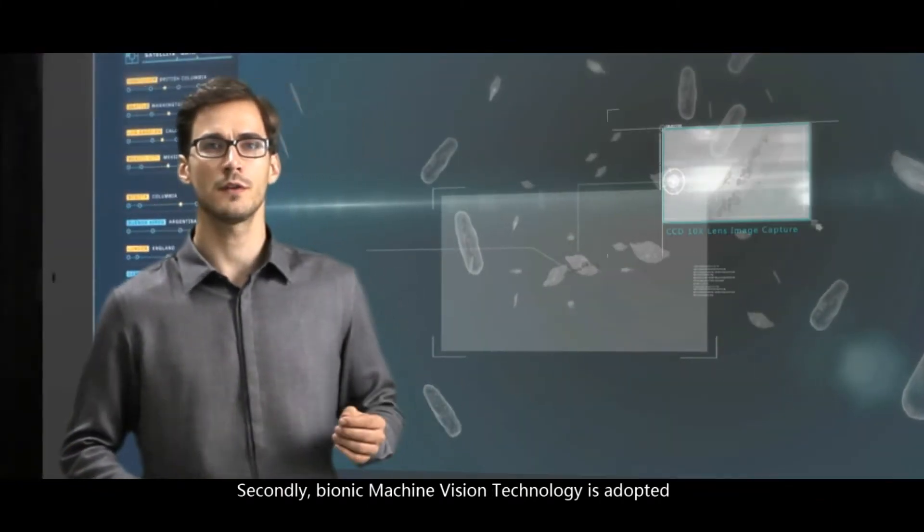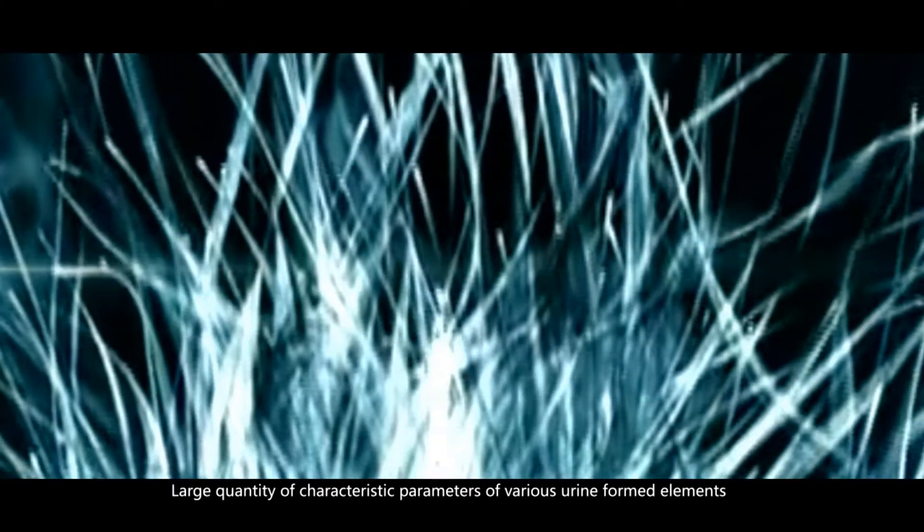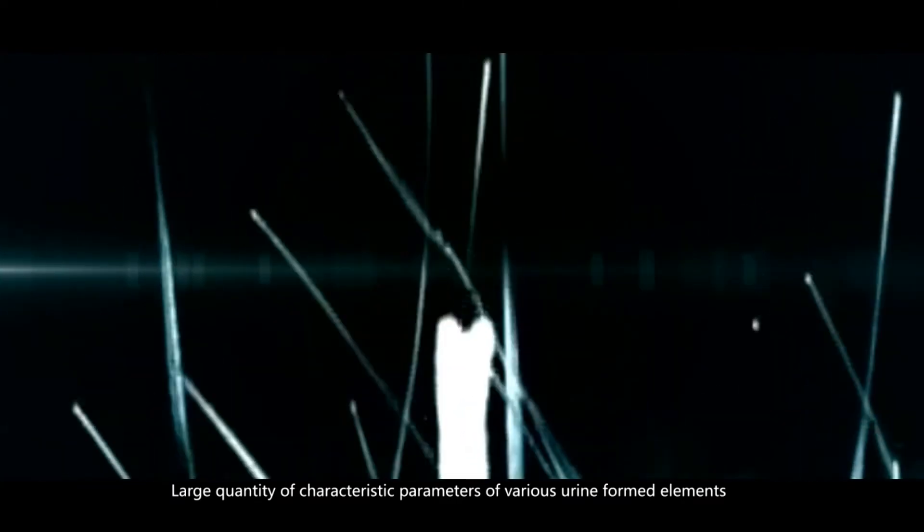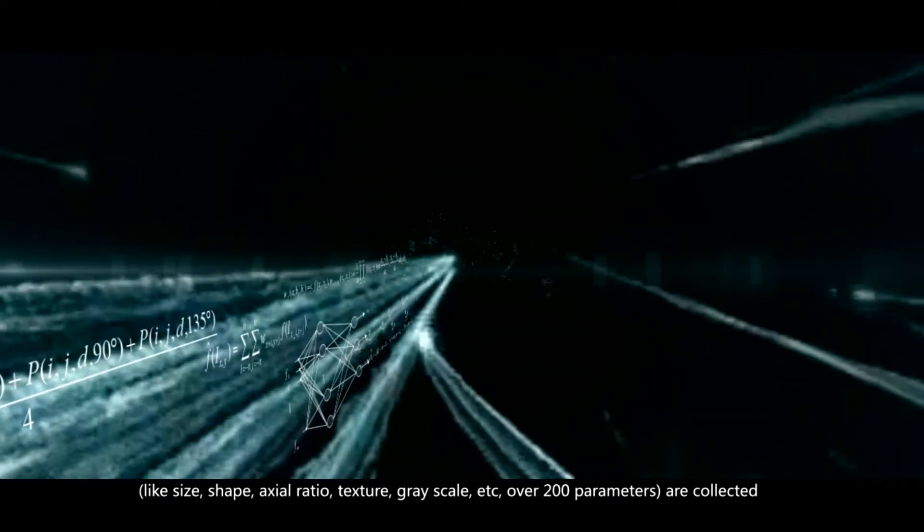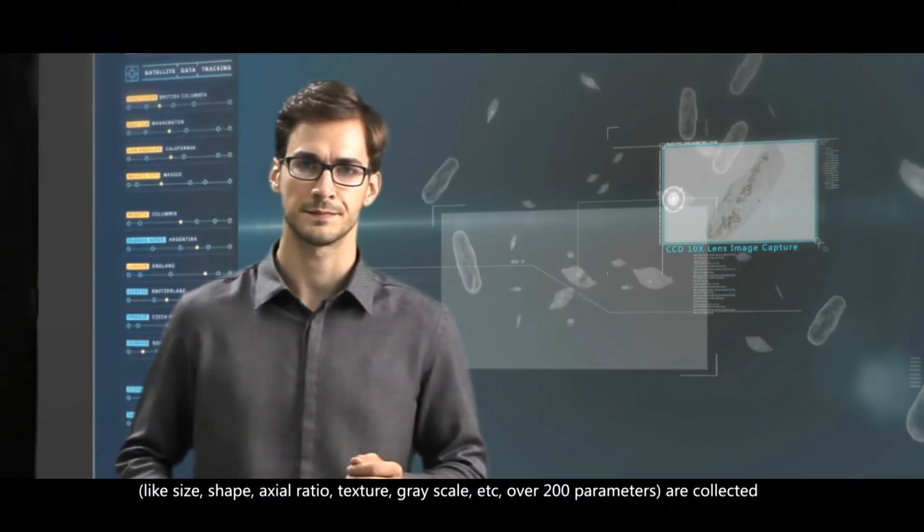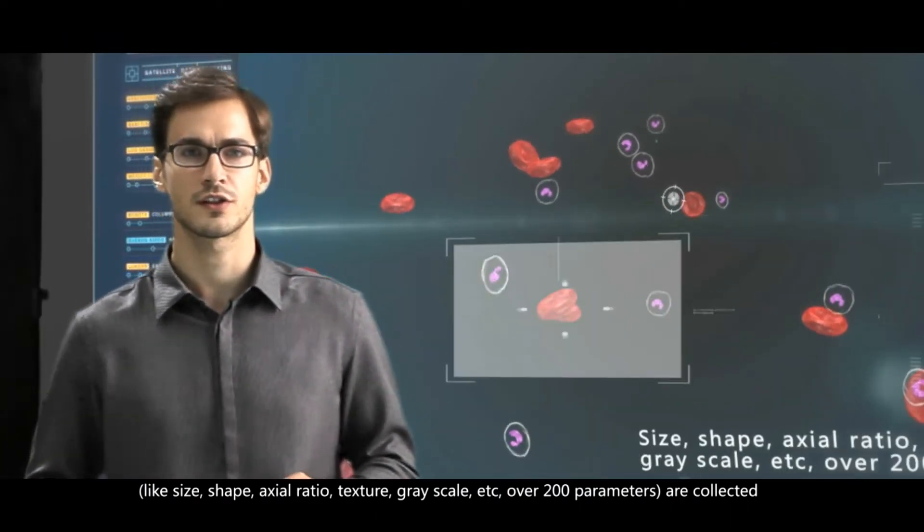Secondly, bionic machine vision technology is adopted. Large quantity of characteristic parameters of various urine-formed elements, like size, shape, axial ratio, texture, grayscale, etc.